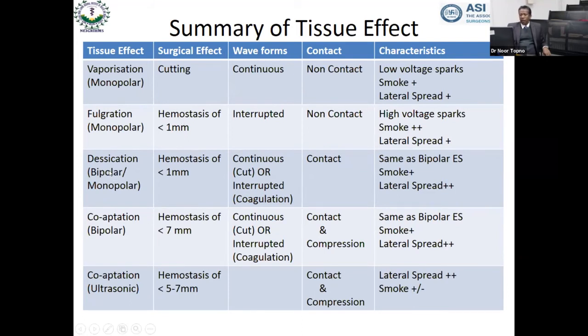Desiccation, again, you can get both in the bipolar mode and the monopolar mode. And the tissue effect is usually one of coagulation or hemostasis. Here, the flow is either continuous or interrupted. Coaptation is a newer technology, which is seen exclusively in bipolar current. And here, basically, it's used for hemostasis.